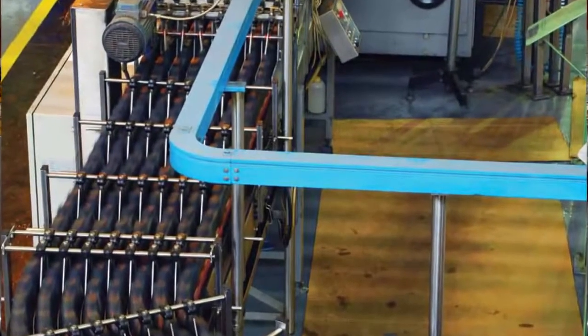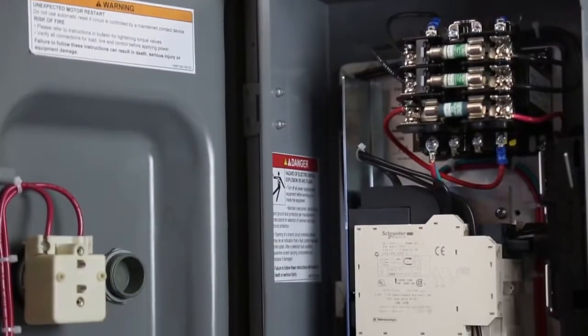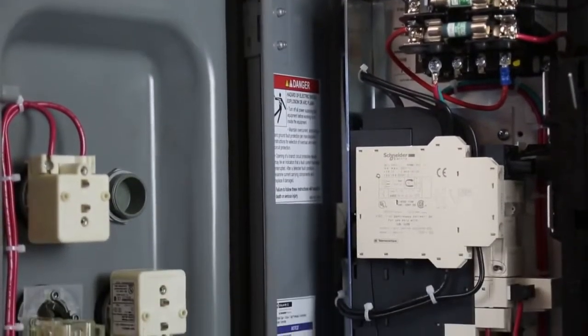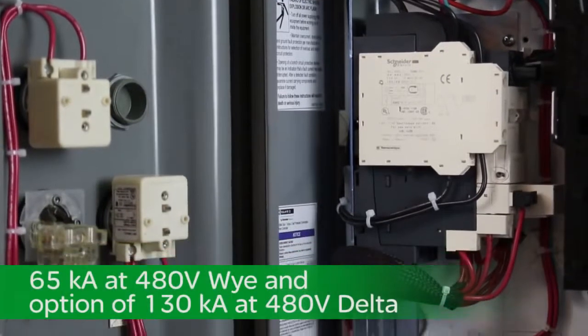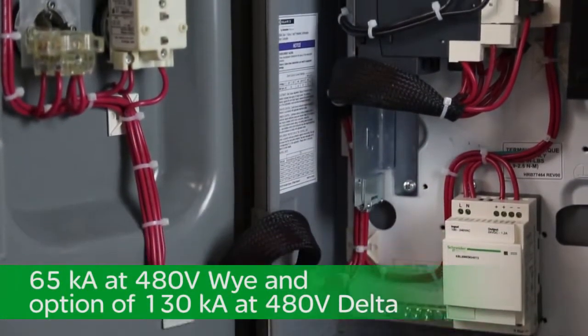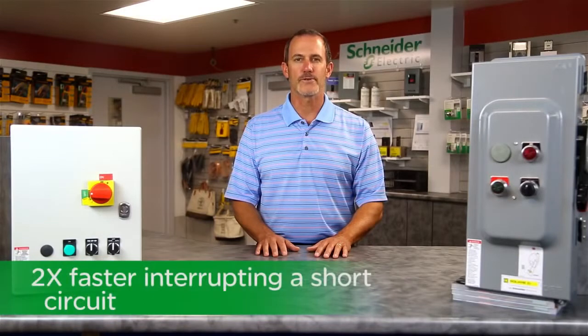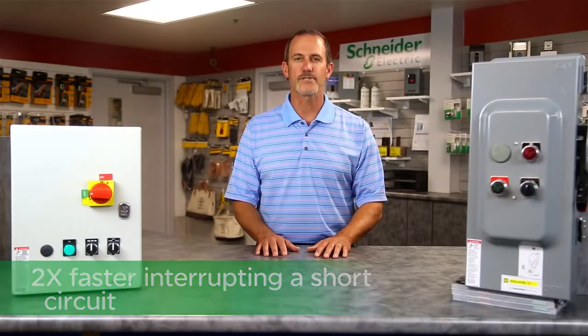Schneider Electric is also focused on reducing your equipment's downtime. The TeSys self-protected motor starter is rated 65 kA at 480 volt Y, with an option of 130 kA at 480 volt delta, according to UL 508 Type E. This means the current-limiting motor starter is ready to restart your system immediately after a fault is cleared.